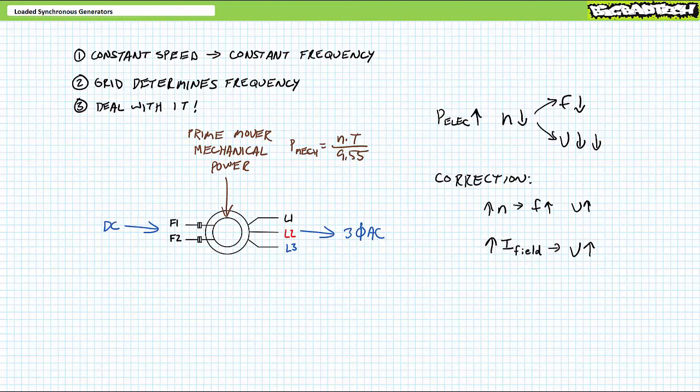Ideally, an operator should be able to pour enough mechanical power into the prime mover by adjusting the pitch of a turbine blade or opening up a valve so it speeds up to the desired frequency specification, and then adjust rotor field current excitation so voltage magnitude reaches an acceptable value. Now, this isn't as easy as it sounds. To suggest that an operator control system is going to hit both targets, frequency and voltage magnitude, in the first attempt, is somewhat of a reach. The system may adjust speed, then field current, then pending the outcome of this first adjustment, may need to fine-tune speed again, then field current again, in an iterative approach, ideally each successive adjustment being smaller and smaller in magnitude. Eventually, the system should stabilize to meet the needs of that load scenario.